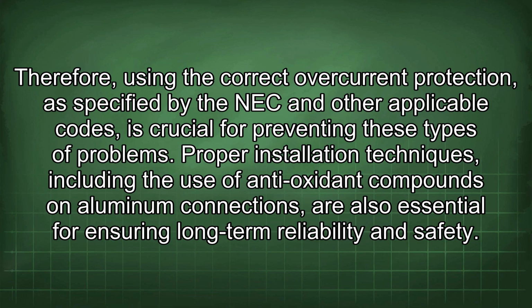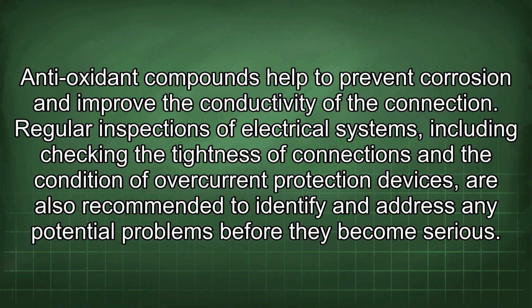Therefore, using the correct overcurrent protection, as specified by the NEC and other applicable codes, is crucial for preventing these types of problems. Proper installation techniques, including the use of antioxidant compounds on aluminum connections, are also essential for ensuring long-term reliability and safety. Antioxidant compounds help to prevent corrosion and improve the conductivity of the connection. Regular inspections of electrical systems, including checking the tightness of connections and the condition of overcurrent protection devices, are also recommended to identify and address any potential problems before they become serious.